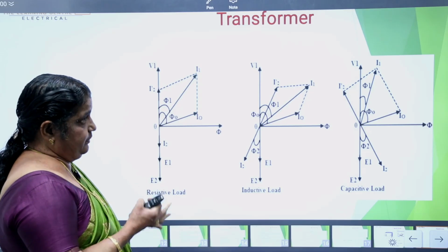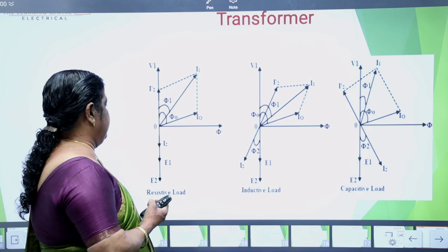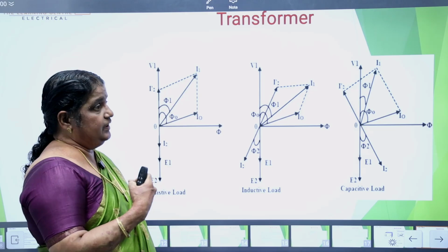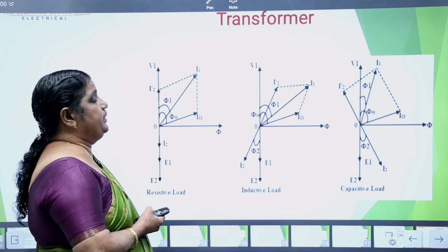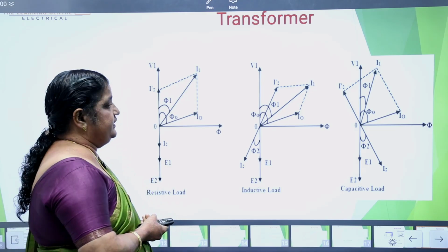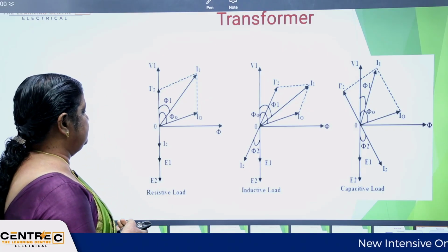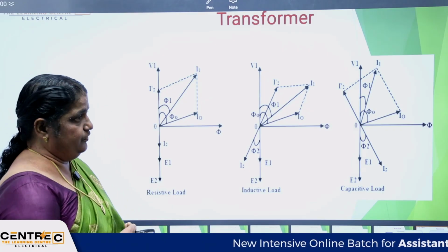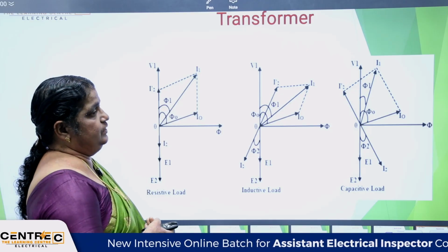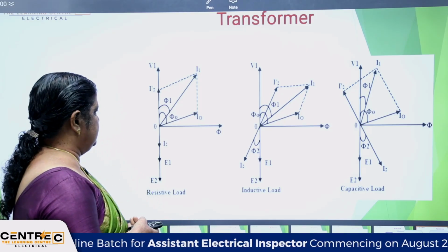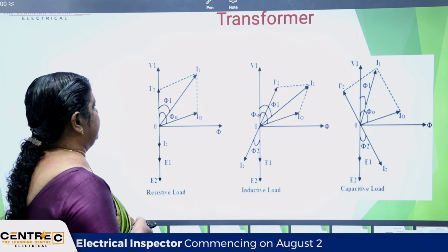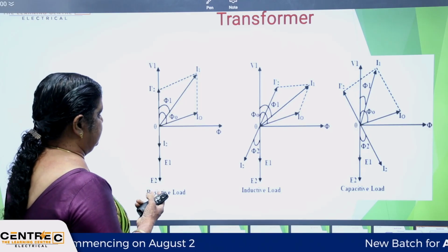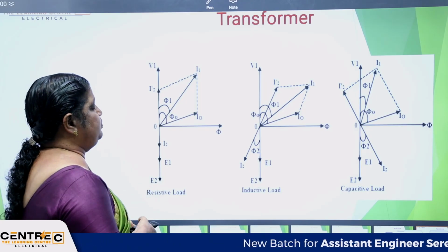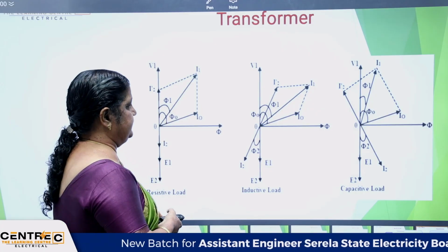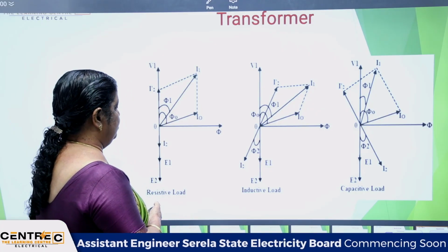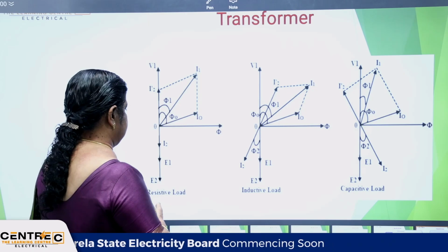We know that I2 converted into the primary side is called I2 dash. The total current or input current passing through the transformer is the vector sum of the secondary current and the no load current, that is the magnetizing current. The vector sum of I2 dash and I0 is called I1, the input current or primary current of the transformer. Here the power factor is unity, that is phi angle 0.